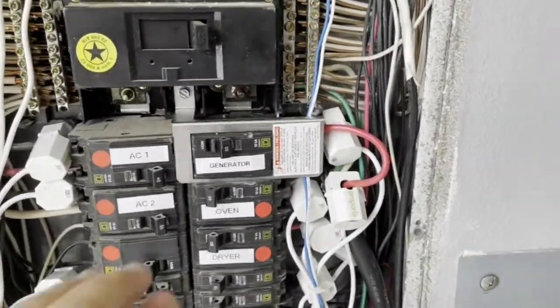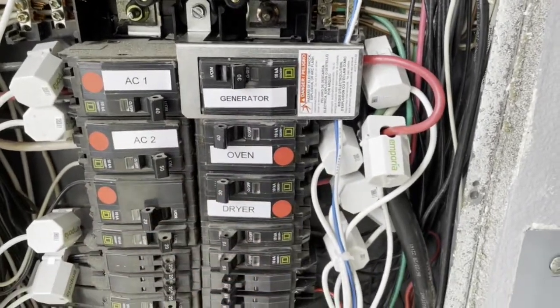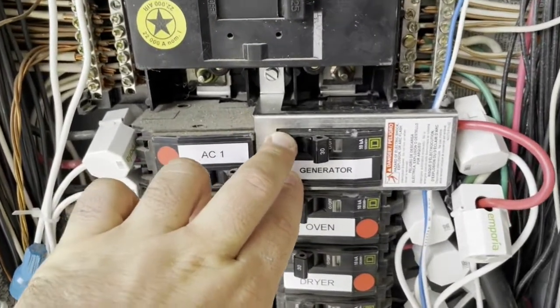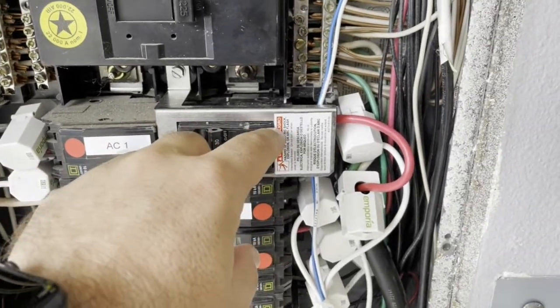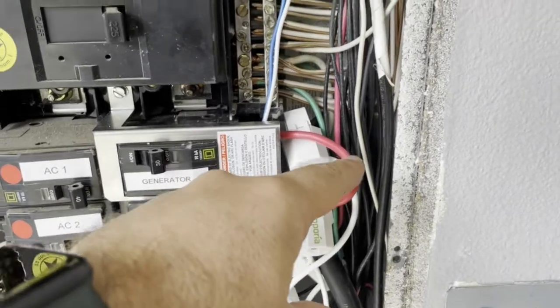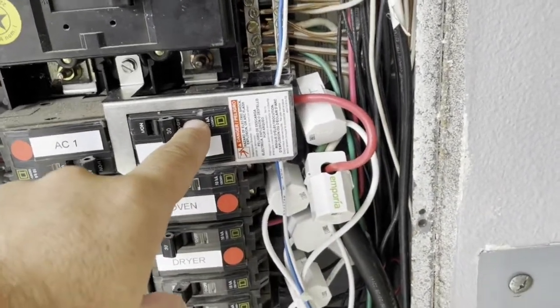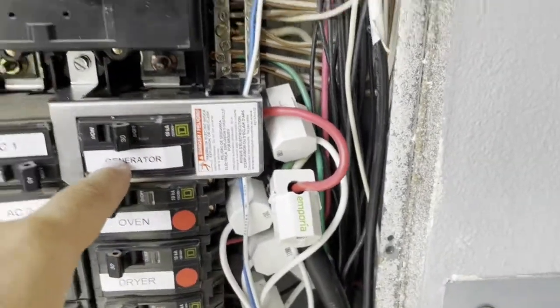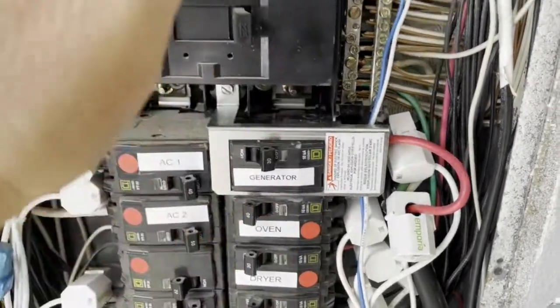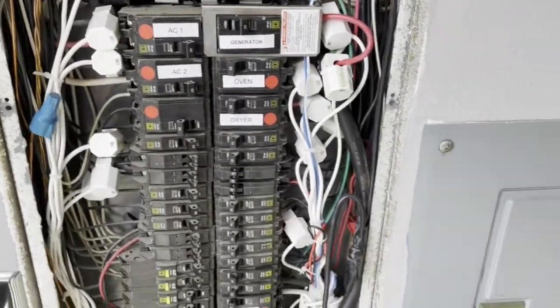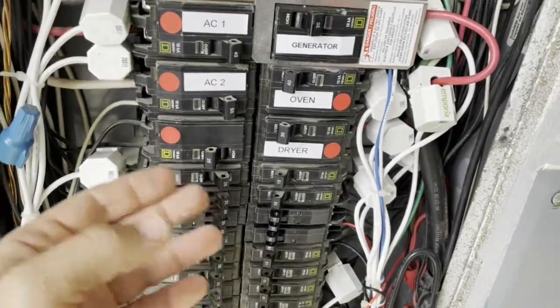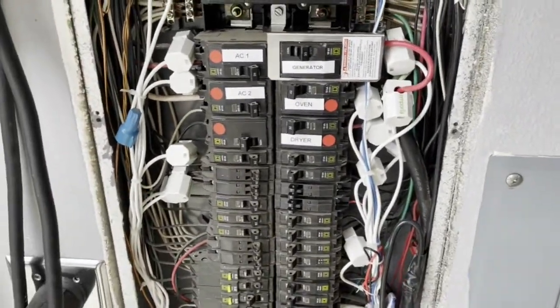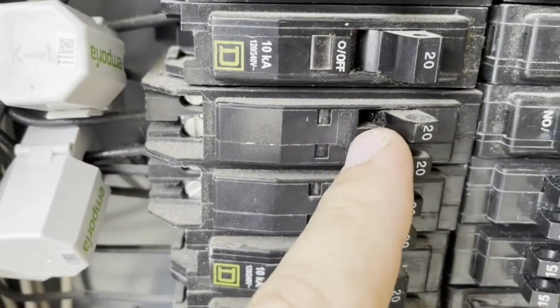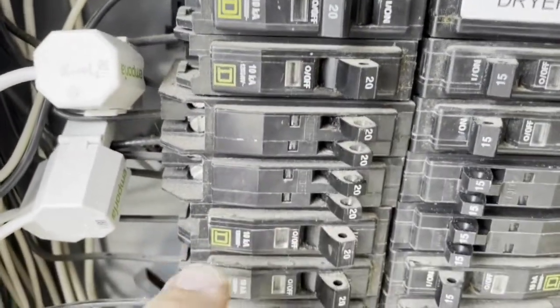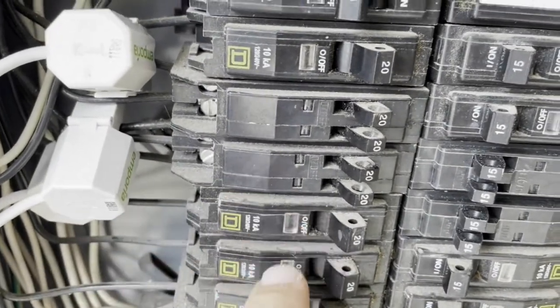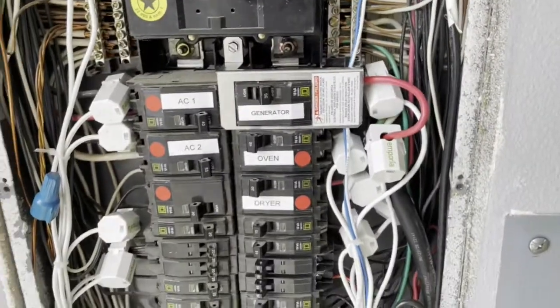Once you may need to move some of your circuit breakers down so that you have two slots free here for the generator. Again, one cable is coming from the generator. The red one is 120 volts, and then there's the black one, which is another 120 volts, and it's feeding all this panel with 240 volts. Some circuits use 110, which is taken from here. If you don't have space in your panel, these double breakers are called tandem breakers. So you can just put two loads into one, and then you can create space using those tandem breakers.